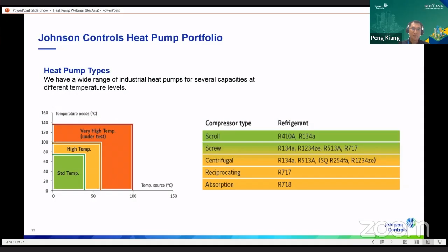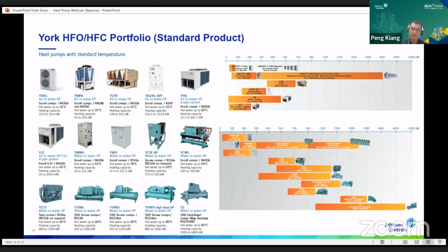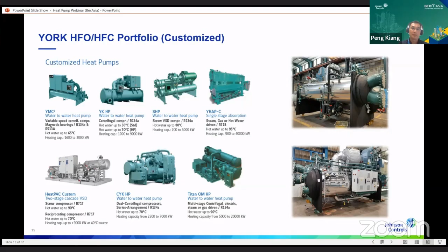And also some water to water heat pump, which is using primarily some HFO refrigerant for lower heating temperatures, about 50, 60, maybe to the highest about 80 degrees C, depending on the type of high pressure screw we're using. And a bit of some customized heat pump as well for some very large heating, high temperature profile. You could have multi-stage centrifugal compressors that can generate hot waters up to maybe 90 degrees C. And in terms of capacity, scale it up to about maybe 5 megawatts to 20 megawatts of heating capacity, mainly for district heating applications around European countries, and perhaps in the future in China as well. We're doing major district heating through the use of heat pump.